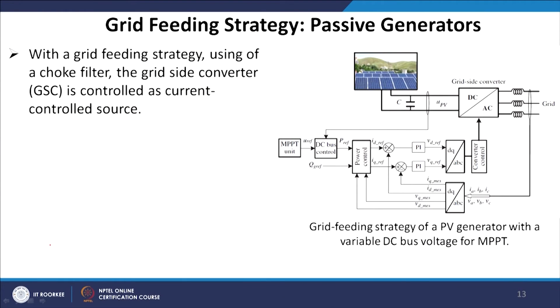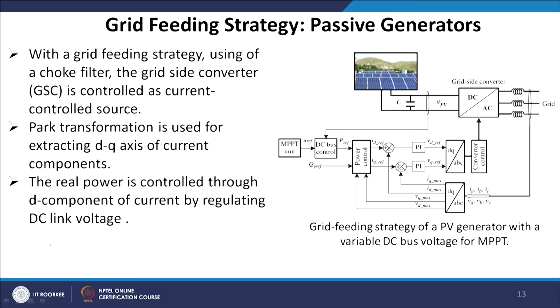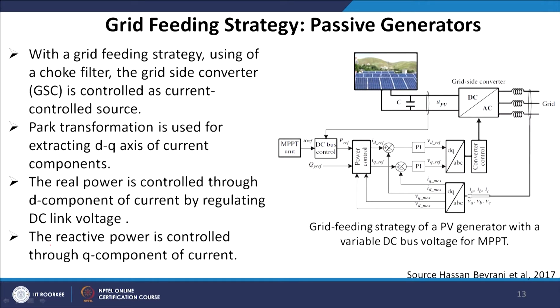For the grid feeding strategy for passive generators using a choke filter, the grid side converter (GSC) is controlled as a controlled current source. Park transformation is used for extracting D and Q axis current components. The real power is controlled through the D component of current by regulating DC link voltage, whereas the reactive power is controlled through the Q component of current.